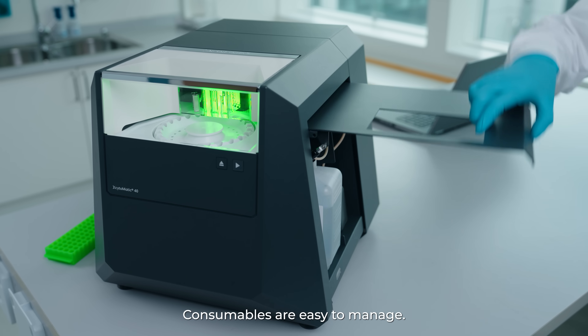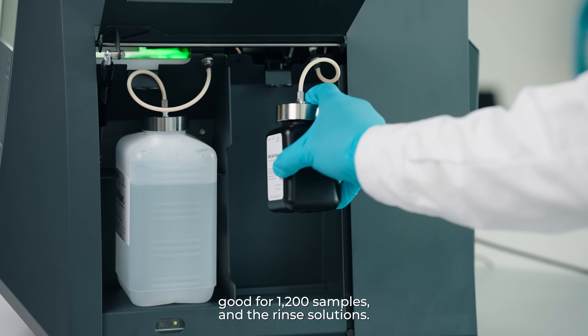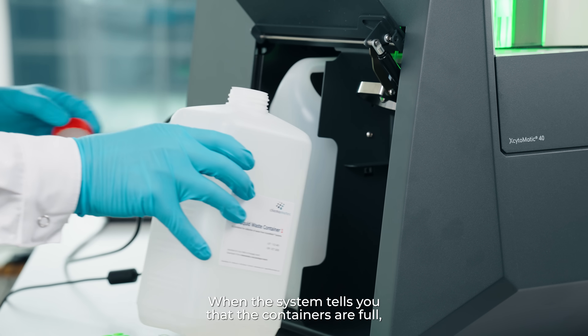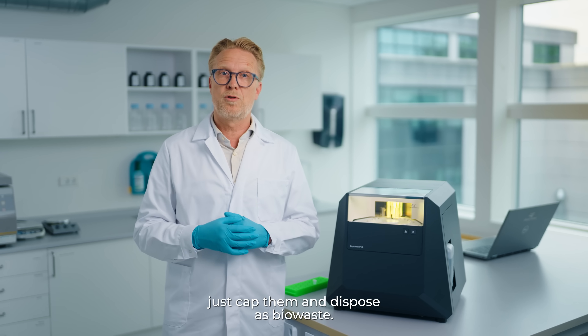Consumables are easy to manage. On the right hand side, we have the staining solution, good for 1200 samples, and the rinse solutions. On the left hand side, we have the waste containers. When the system tells you that the containers are full, just cap the containers and dispose as biowaste.